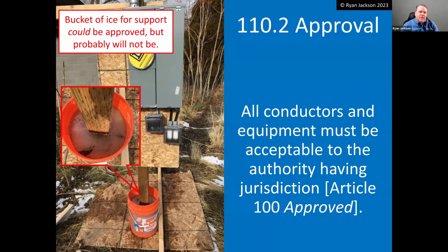So here we've got this temporary installation. A friend of mine, an inspector in Salt Lake City, sent me this picture. They went out to do this inspection, and believe it or not, they were supporting this temporary wiring with a bucket of ice, which I guess kind of puts a time limit on it. You know, at least I know this thing's not going to be here all year. You know, this project better be done by April or so. But you know, the code doesn't really talk about whether or not you can use a bucket of ice. So it does rely on the authority having jurisdiction to make a decision, right? So things have to be approved, and that's where 110.2 comes in.